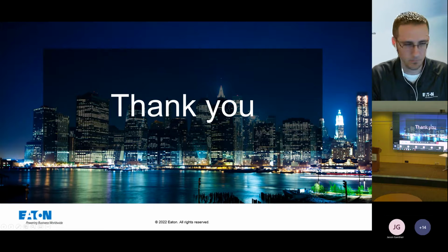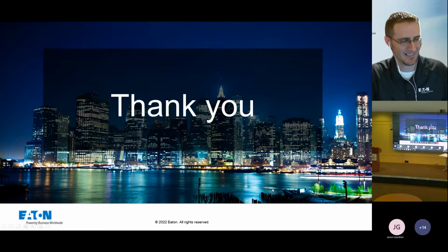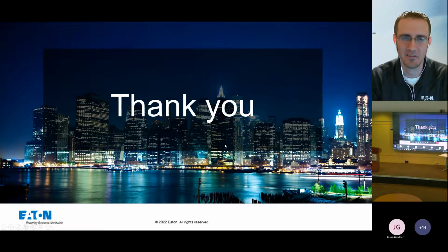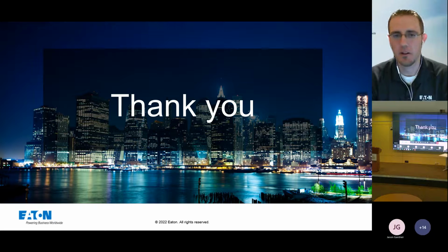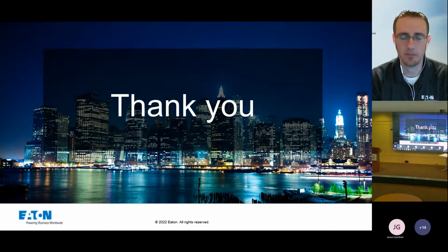Steve Roach with PSC, interested in the lead times, since that's everybody's biggest concern right now. As far as VRLA versus lithium-ion, if I ordered something today, what am I likely to get first? That's going to depend specifically on the model, that's the best answer I can give you. We have stock of some models of both VRLA and lithium, and no stock of others with long lead times. I'll say some of the global models with higher voltages, say 208 volt, might have a little bit longer lead time. We're recovering on those, but it really is model specific. So if you had something in mind, a 1500, a 2000, a 3000, and wondered if we have one or both available, let me know and we can get those answers for you.